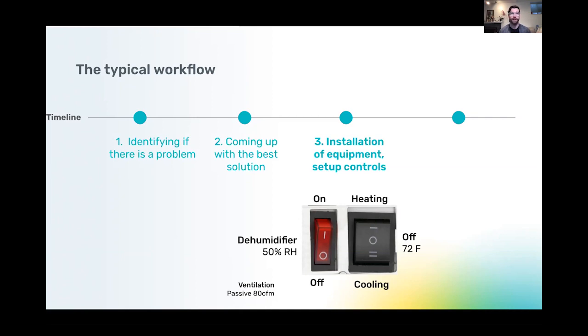What that effectively does is it heats up the air on a reheat system right before it enters the evaporator coil of the air conditioner, and it makes the central air conditioner ineffective, and it makes the entire system ineffective, and it increases your energy bill substantially because it's constantly producing hot air and making the air conditioner run constantly. So that's one example of you can do it wrong. There are many cases of dehumidifiers being installed wrong, and the only reason it was noticed is because the energy bill skyrocketed and the homeowner noticed that.